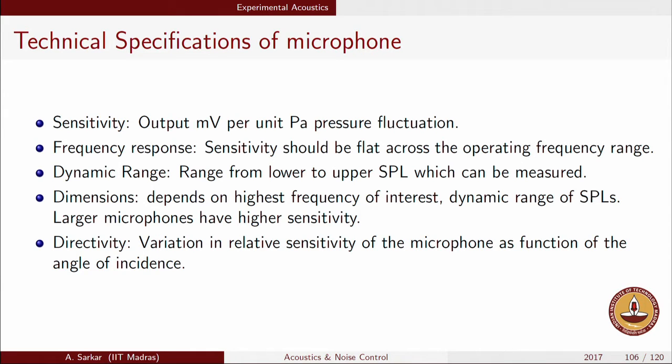Directivity of free field microphones is very important, and manufacturers report the variation in sensitivity for different angles of incidence. It is recommended to use the microphone facing the incident wave normally. You would like to know the range of possible errors if you go off-angle, keeping sensitivity change within certain bounds. This directivity issue does not apply to pressure field microphones, which work in an omnidirectional fashion.